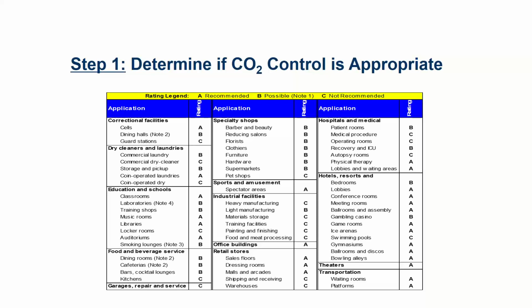The bad candidates typically either lack variability in occupancy or have non-people pollutants that are pretty harmful. For example, a prison guard station is a bad candidate, everybody has to be there, no variability. Dry cleaners are bad too, the heavy ventilation isn't because of the two people working in the back, it's because of the chemicals. Locker rooms and pet shops already smell horrible, so don't cut the ventilation rate back there.